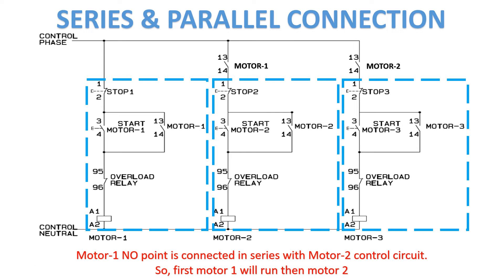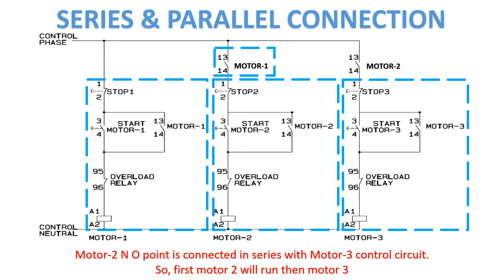Motor 1 NO point is connected in series with the motor 2 control circuit, so first motor 1 will run, then motor 2. Motor 2 NO point is connected in series with the motor 3 control circuit, so first motor 2 will run, then motor 3.